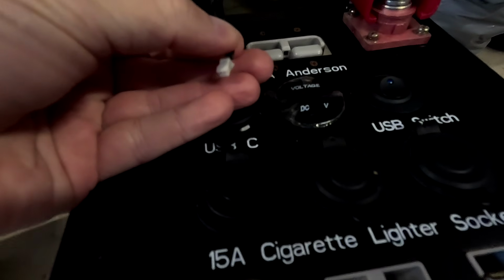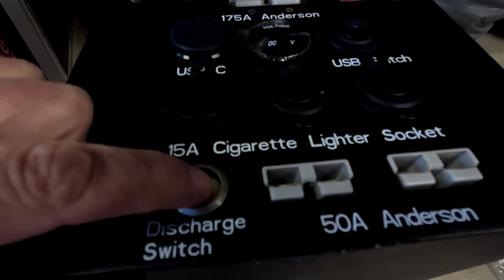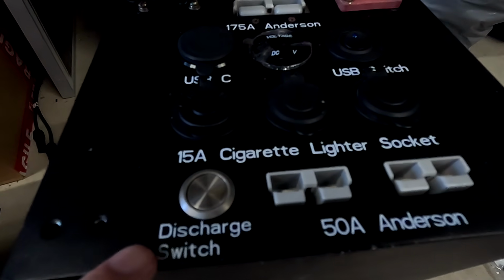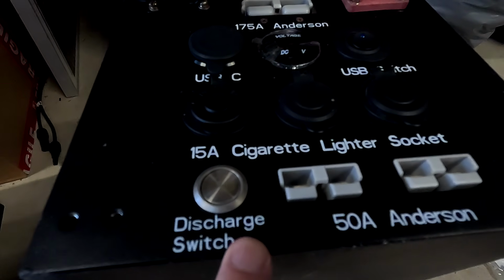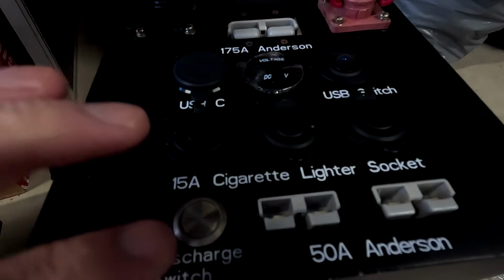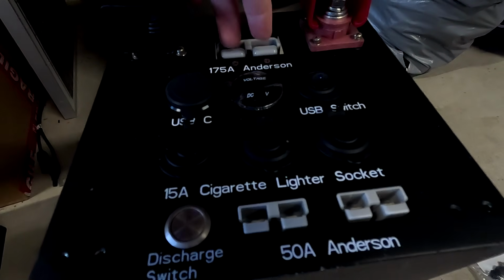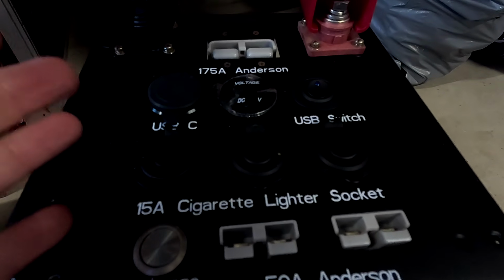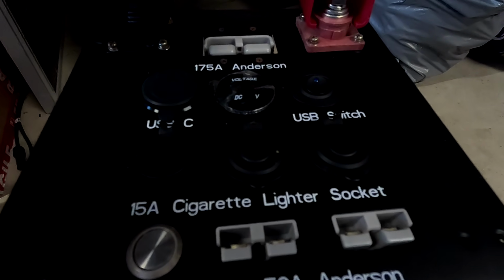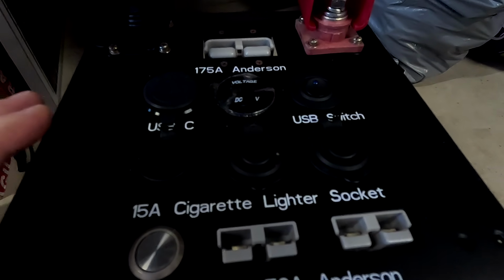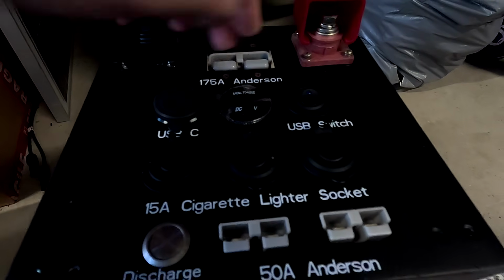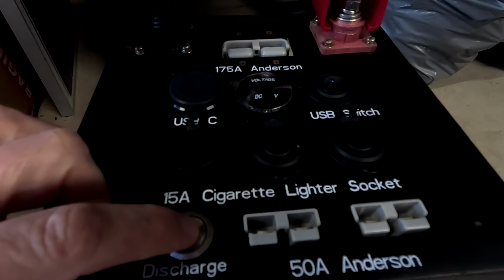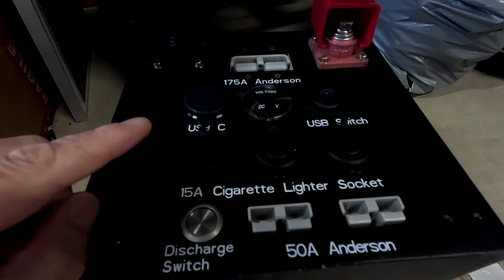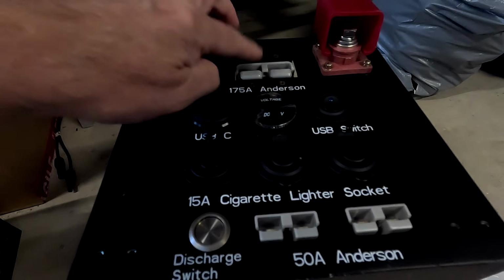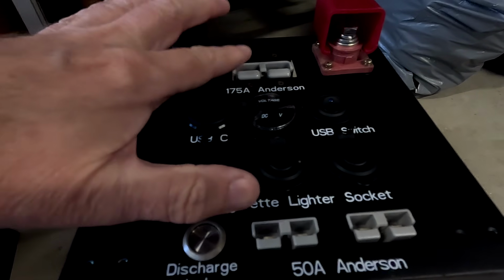This is just a 2-wire cable which was connected to the Daly BMS, and by releasing this button we could actually disable the discharge MOSFETs of the BMS. This is especially handy if you connect an inverter, because with the discharge MOSFETs in the BMS turned off, you're not getting an inrush current. So you connect your inverter here and then turn on the discharge switch again, and the BMS takes care of the inrush current. So there's no sparking, no fear, no tears.